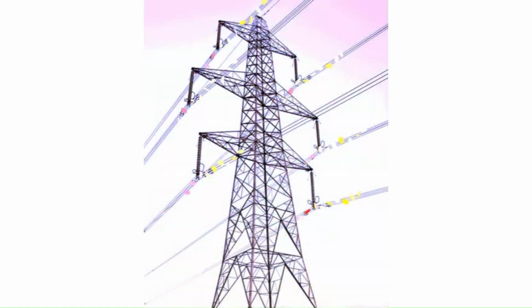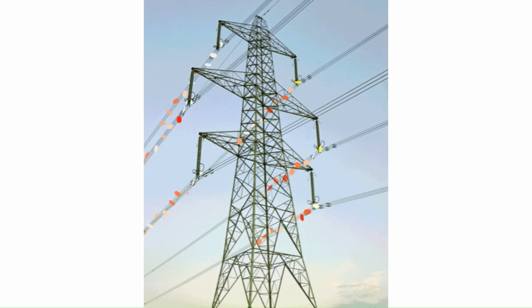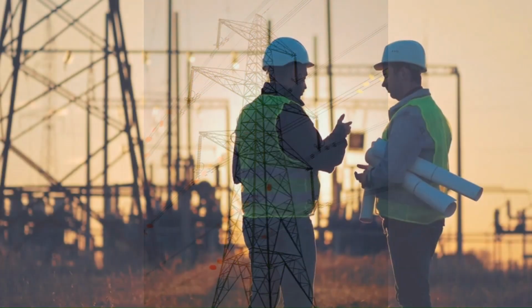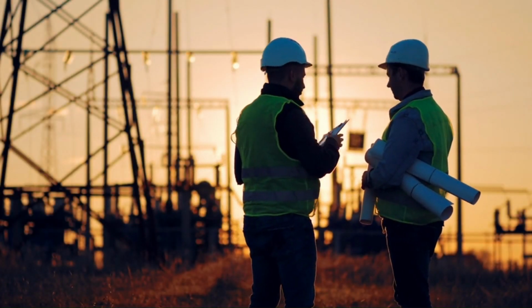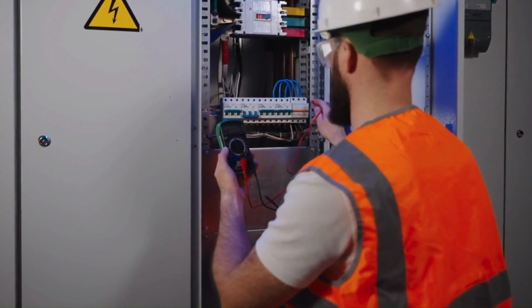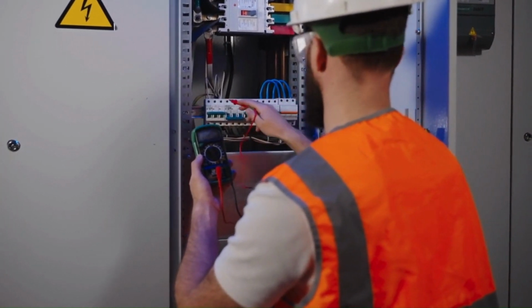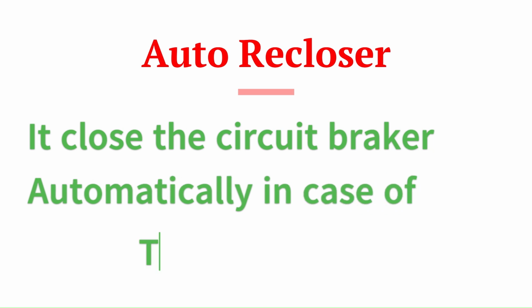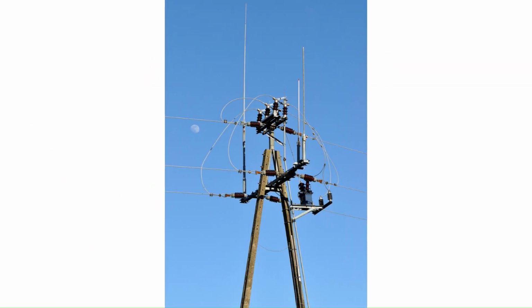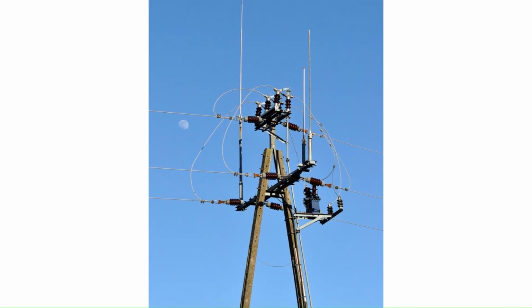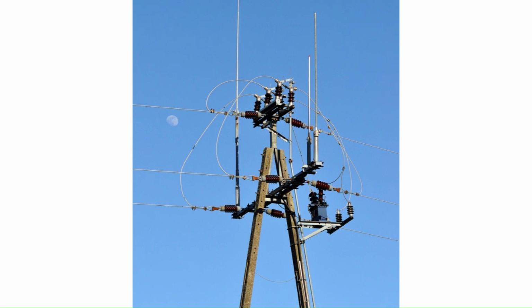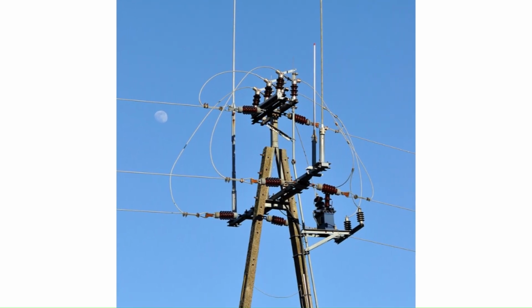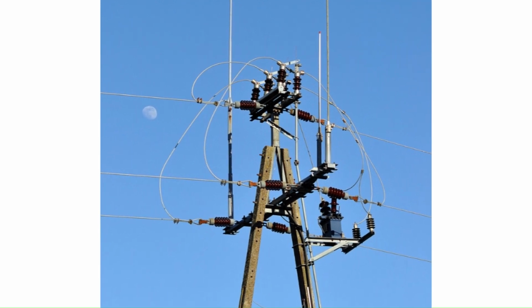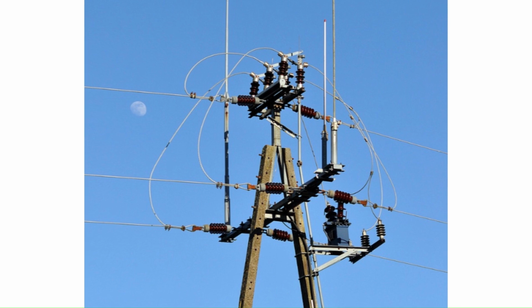In overhead transmission systems, nearly 80% of the faults are transient in nature. Therefore, it is practically not possible to close the circuit breaker manually every time, and any delay in manual reclosing can cause loss in the cost and stability of the system. Auto reclosing plays an important role to close the circuit breaker automatically in case of a transient fault. An auto recloser is a switchgear device that automatically and quickly restores power after tripping of the circuit breaker by a transient fault. If the fault is permanent, the recloser will go into a lockout state and require manual reset.